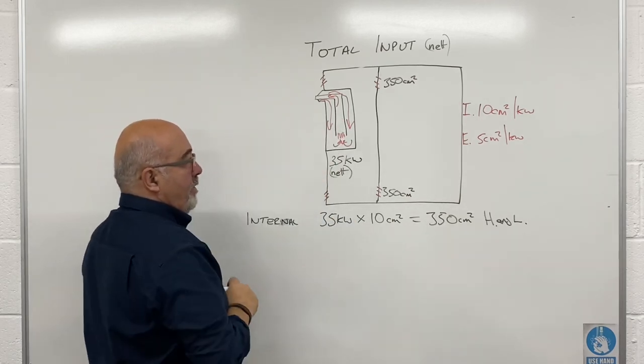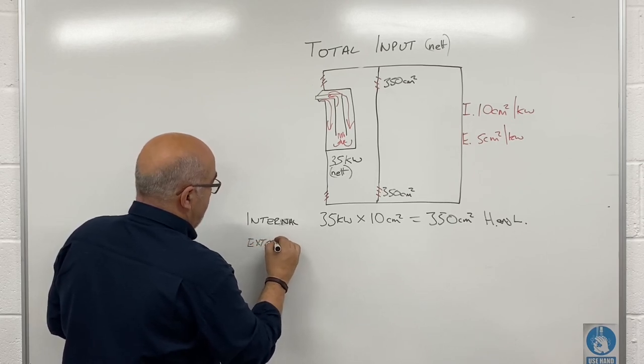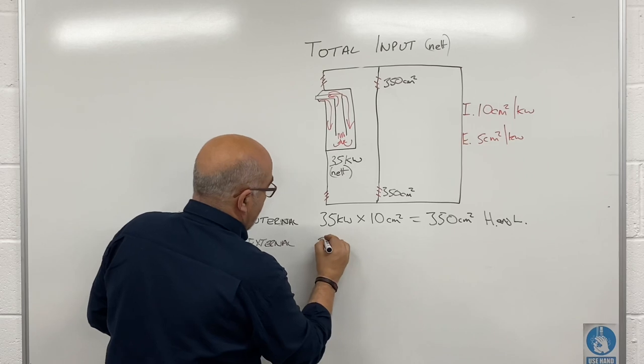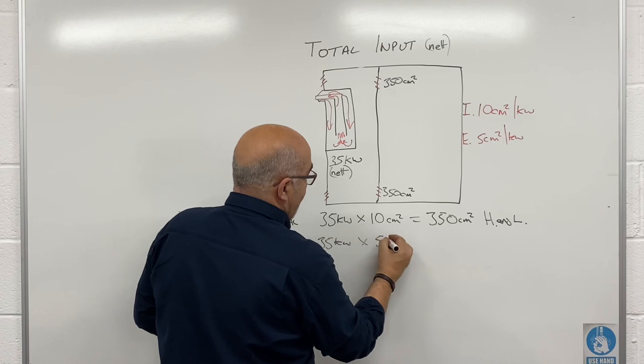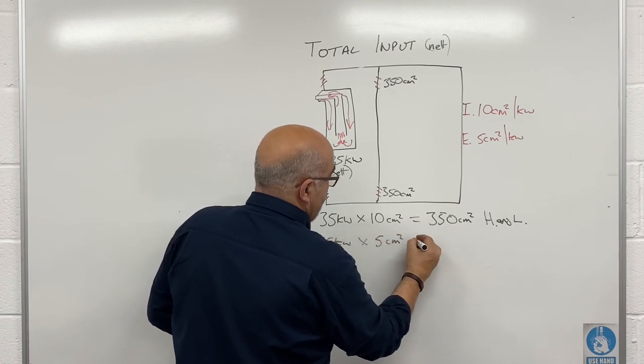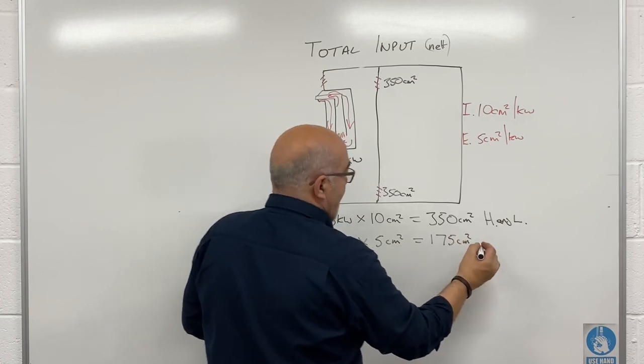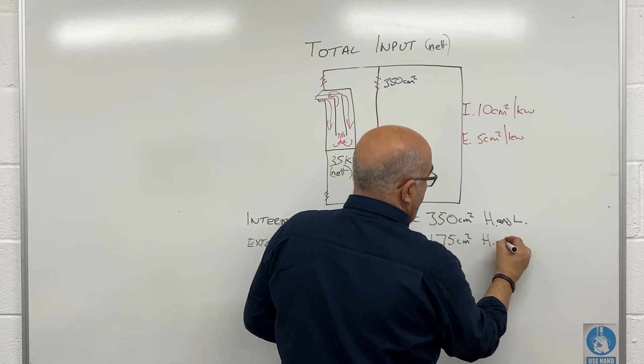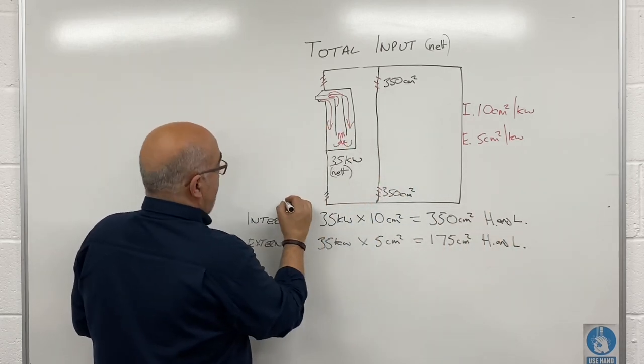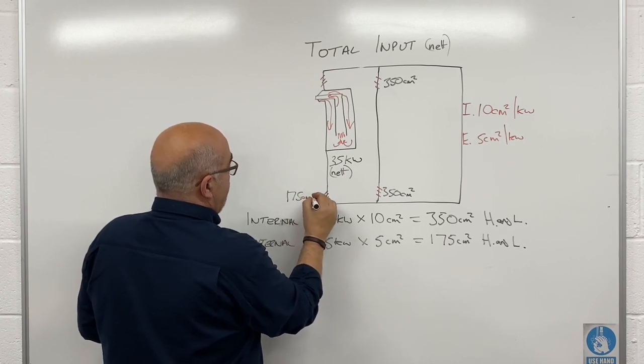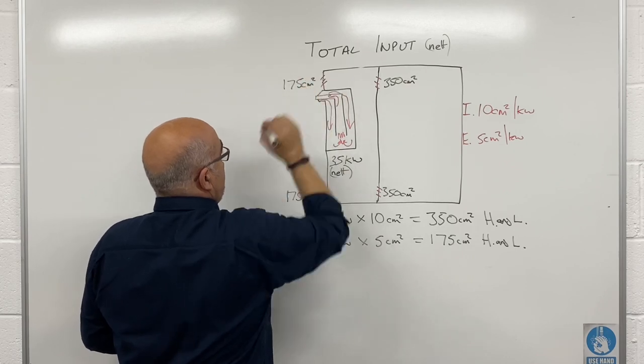Externally, using the same boiler: 35 kW total input multiplied by 5 cm² equals 175 cm² of free area. Again, that would be high and low — 175 cm² at the top and 175 cm² at the bottom.